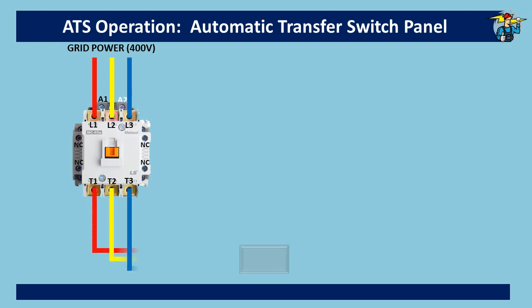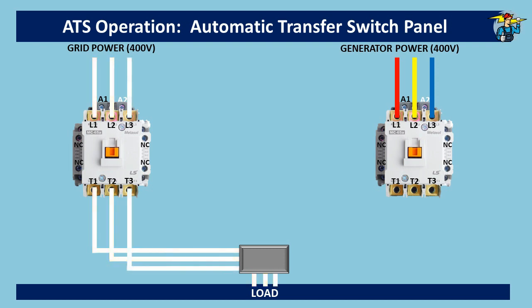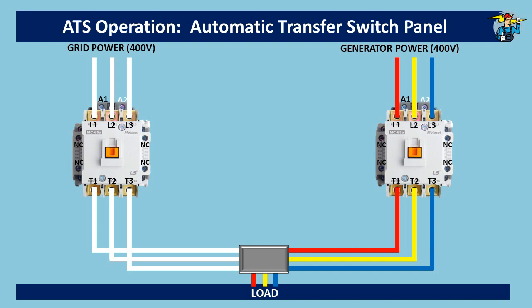When the grid contactor is in the ON position, the load is connected to grid power. If we start the standby generator, power will be available up to the L1, L2, and L3 terminals only, since the generator contactor is at the OFF position. If grid power goes off, we need to connect power from the generator to the load automatically, and vice versa.